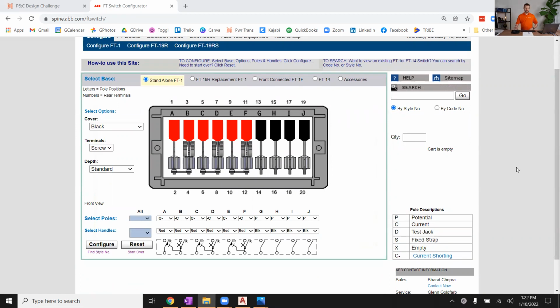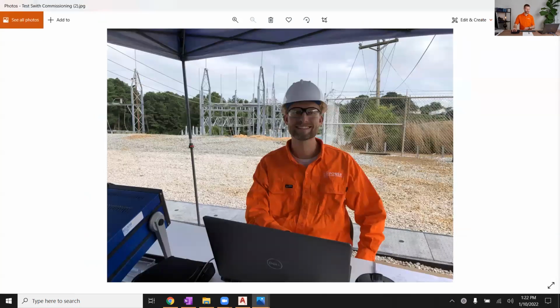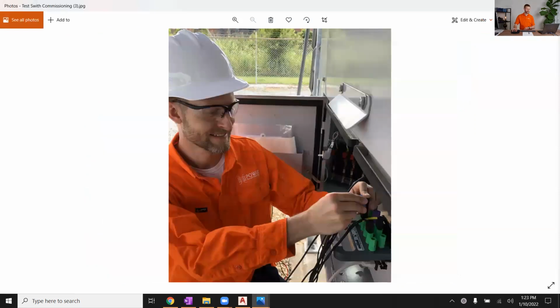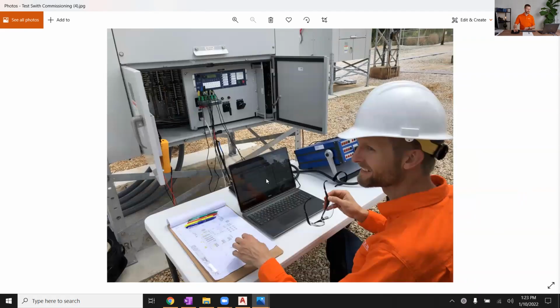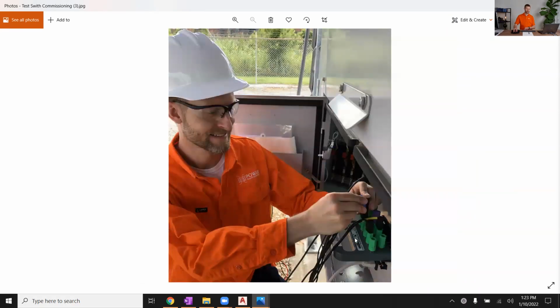And what we're trying to do here is provide a means to isolate the real life primary power system equipment, the PTs and the CTs, from the back of the relay, and then allow us to inject or simulate some test signals into our relay for our relay test plan to be executed. The best way I can probably show you that is a friendly commissioning trip I had last year. I'm sitting out there with an Omicron test set right here, controlling that Omicron test set with my laptop on the Omicron software. And then from the test set, I wired these voltage and current signals into this test paddle, which you squeeze in after you open all those test switches. And all of a sudden, when you open those switches, you've isolated the actual real life CTs and PTs from the back of the relay.